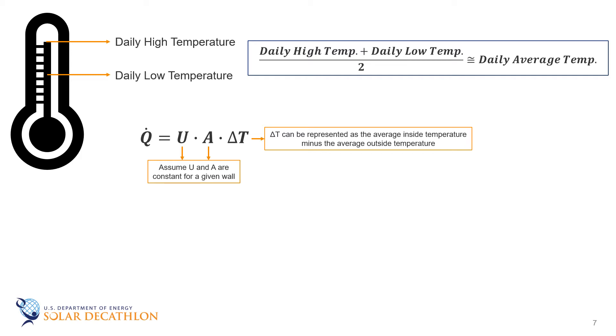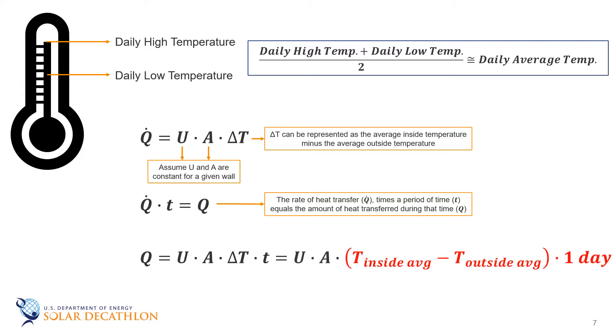If we multiply the rate of heat transfer Q dot times the period of time, that's little t, we will get the amount of heat transferred during that time. Writing this out, we see that Q equals U times A times delta T times little t, which is time. This equation, with t equals 24 hours to represent the day, and the delta T being the inside average temperature minus the outdoor average temperature will approximate the heat transferred during each day.